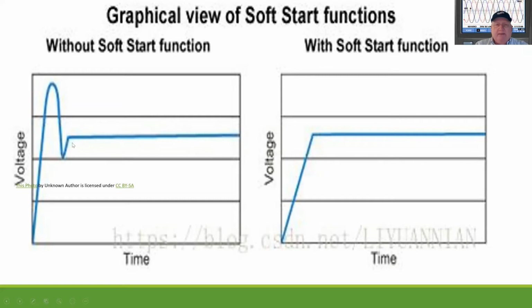And then the more recent ones are the SCR control that I just showed you. So what happens is that we're able to control that voltage ramp as it comes up, and we can spread this out or move it back, how fast we give the motor voltage. What that does is allow the motor to go into more of a slip mode, meaning that you can control its rate of startup.